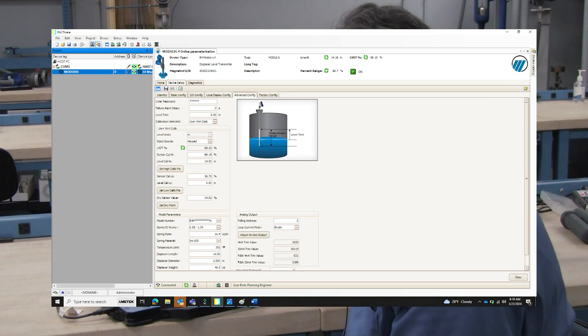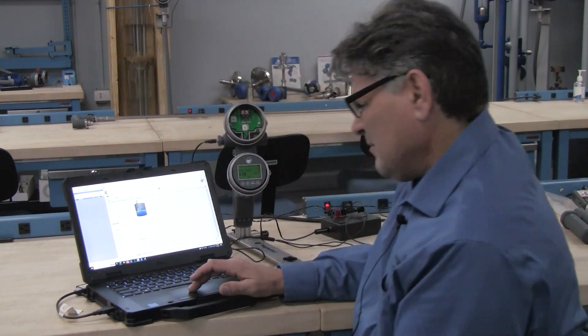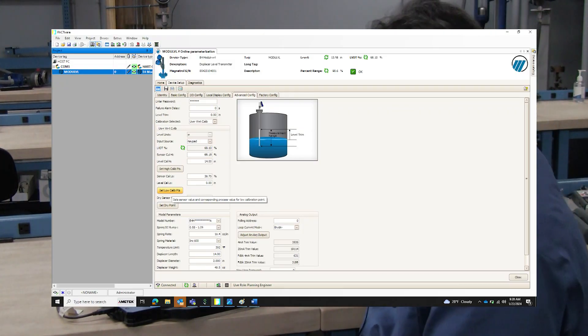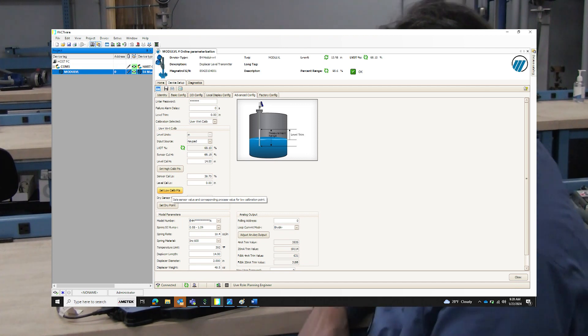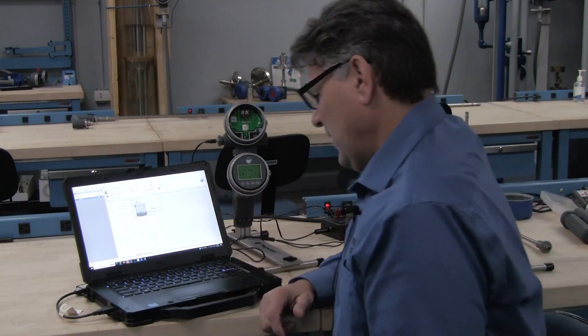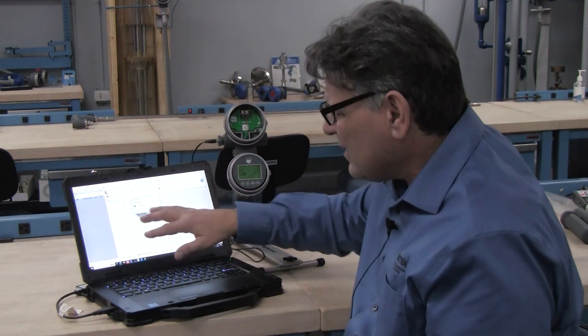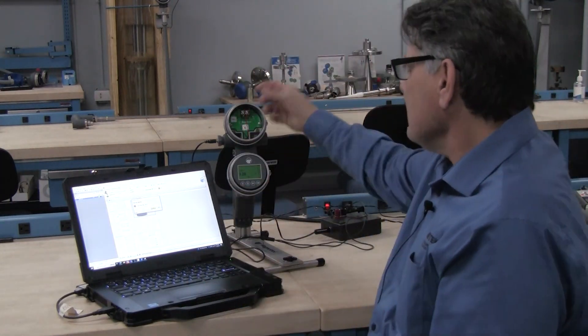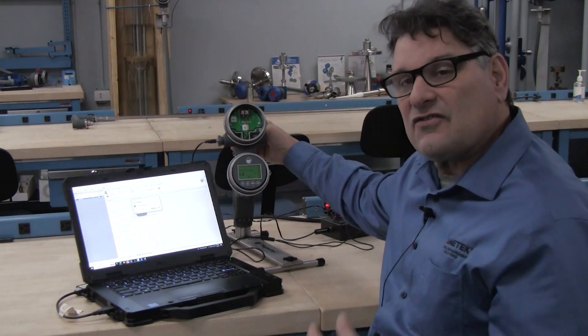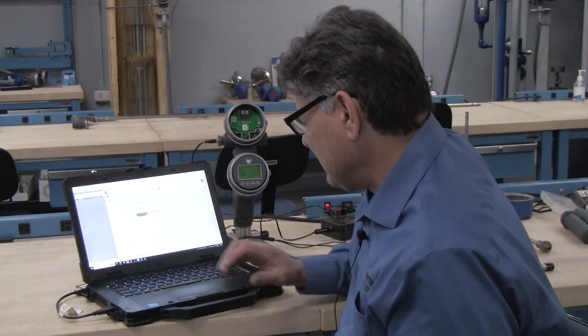So when I enter that, you will see my calibration information come up. And I'm going to go ahead and set my low calibration point since I'm simulating my low level. I simply click this button and it's going to set my low calibration point. And when it does that, what it's looking at, there is a LVDT percentage in these devices. And it goes in and it looks at that and it's going to store the percentage that that LVDT is at.